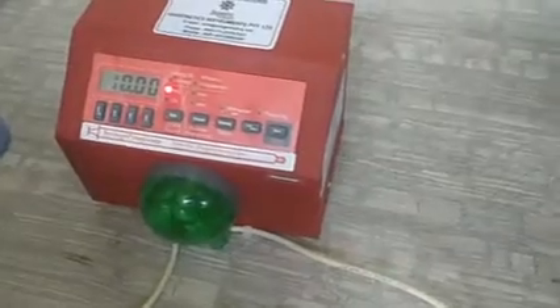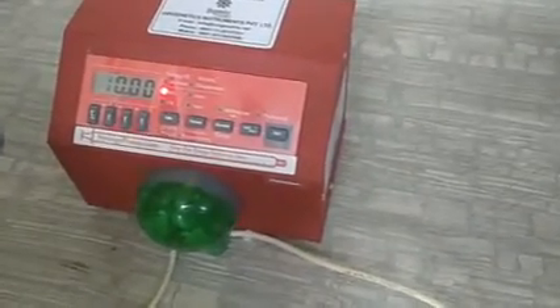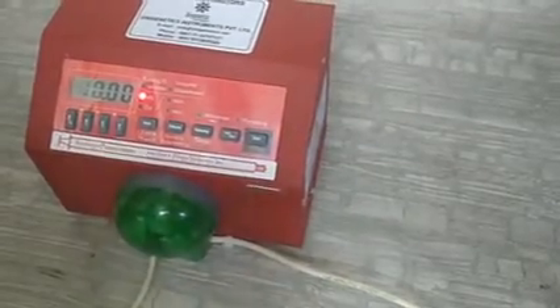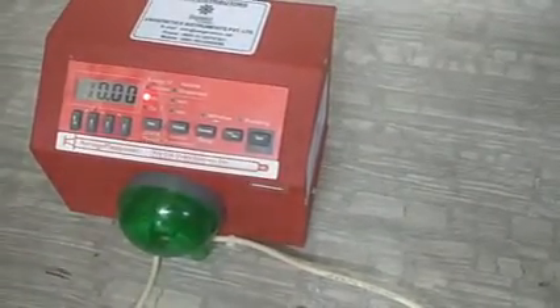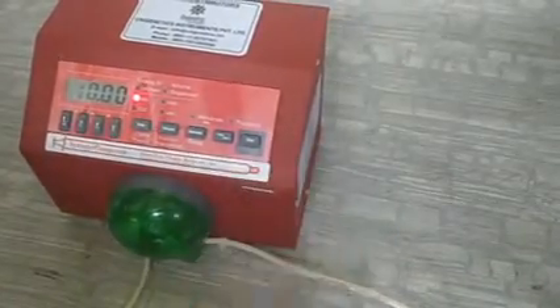Many a time customers use this machine for fraction collection also. Suppose you have to dispense 10 ml, or 2 ml or 5 ml, into different vials. Many people set the flow and the volume and press start every time. But suppose you have hundreds of vials and you don't want to press start every time, you can do programming where it will dispense some volume and after that it will pause, so that in the pause time you can change the vial and again it will start on its own.